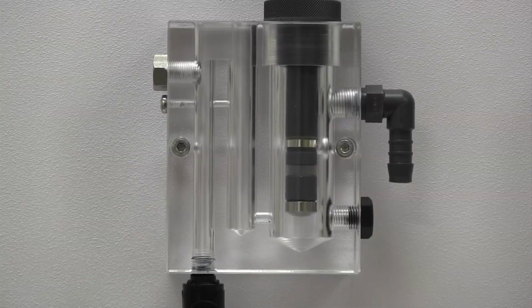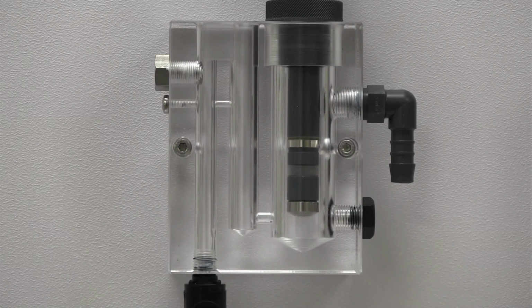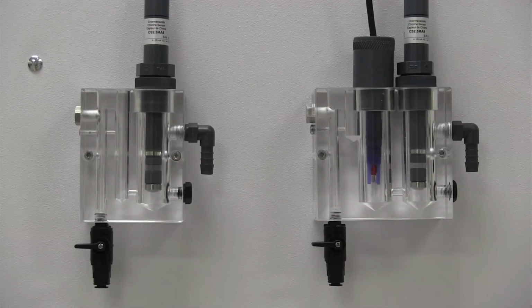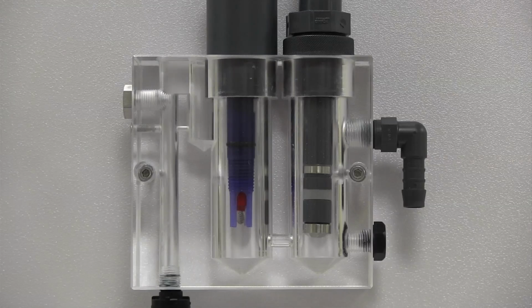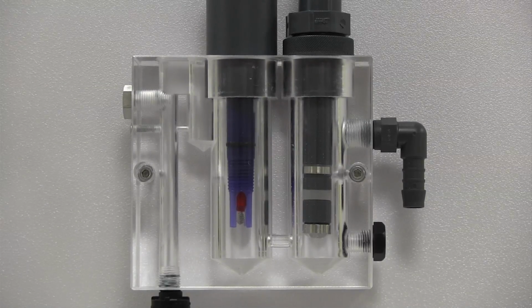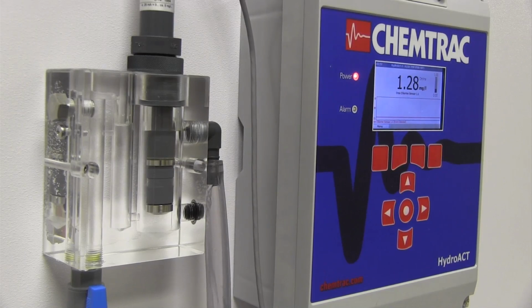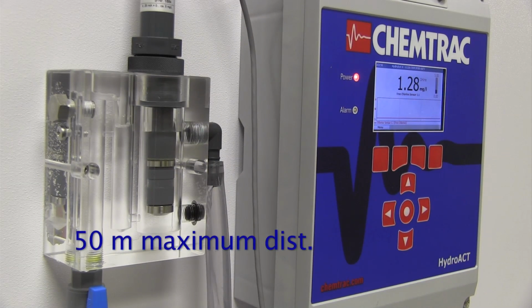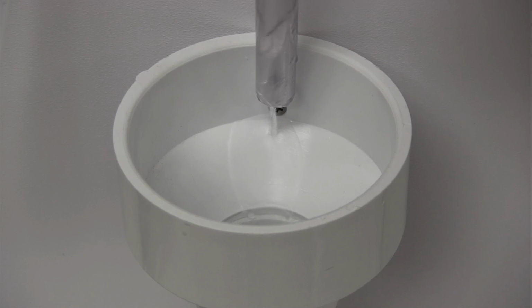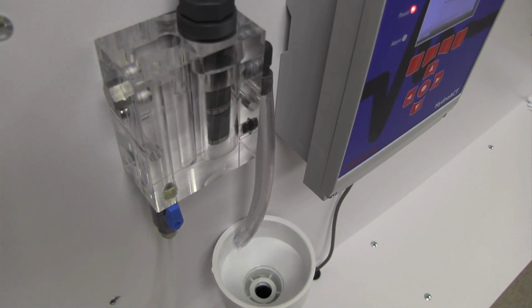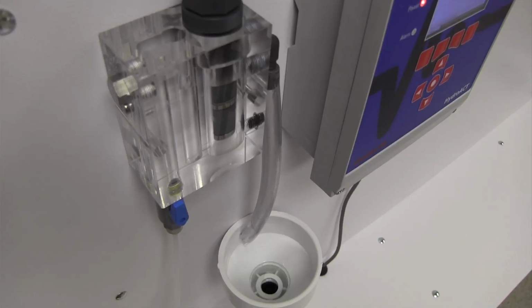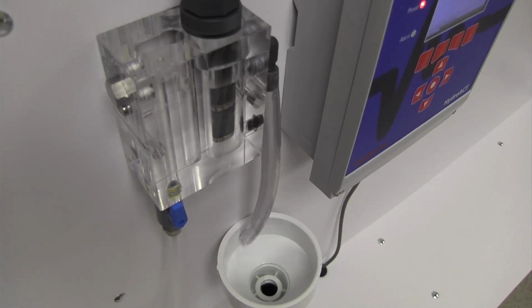The sensor flow cells are essential to the proper performance of the analyzers. A dual chamber model is also available for use with a second probe, such as pH or ORP. For the dual flow cell, the chlorine probe should only be used in the second flow chamber, the chamber on the right. As a general rule, the flow cell should be positioned no more than 50 meters from the Hydroact Analyzer. The sample outlet should flow directly into an atmospheric drain. The flow cell is vented and will not achieve the proper flow rate if there is any back pressure or flow restriction caused by the drain line.